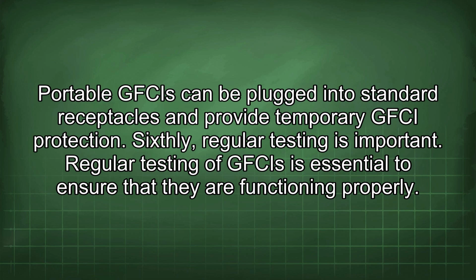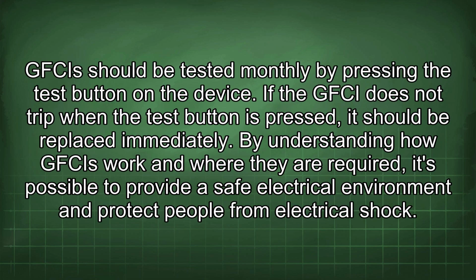Sixthly, regular testing is important. Regular testing of GFCIs is essential to ensure that they are functioning properly. GFCIs should be tested monthly by pressing the test button on the device. If the GFCI does not trip when the test button is pressed, it should be replaced immediately. By understanding how GFCIs work and where they are required, it's possible to provide a safe electrical environment and protect people from electrical shock.